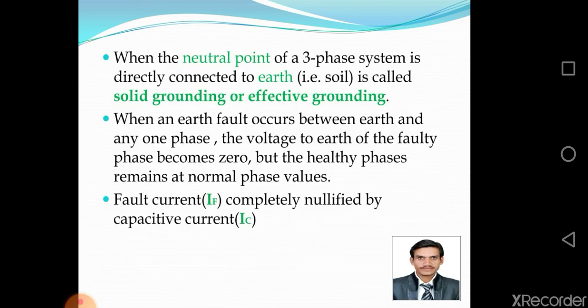When the neutral point of a three-phase system is directly connected to earth, it is called solid grounding or effective grounding. When an earth fault occurs between earth and any one phase, the voltage to earth of the faulty phase becomes zero, but the healthy phases remain at normal phase values. IF represents the fault current. It is completely nullified by capacitive current according to the previous diagram.